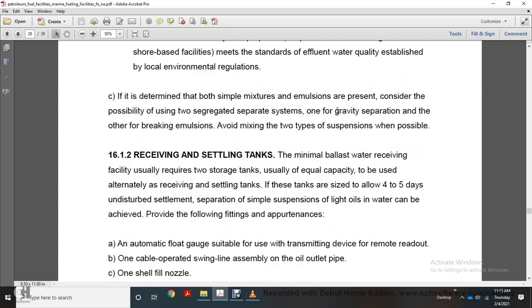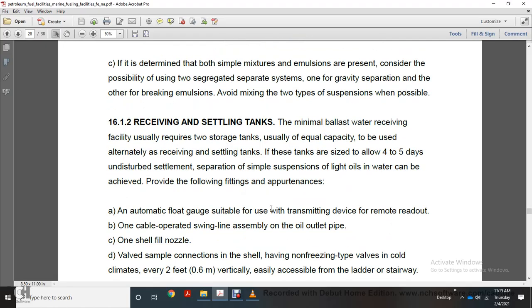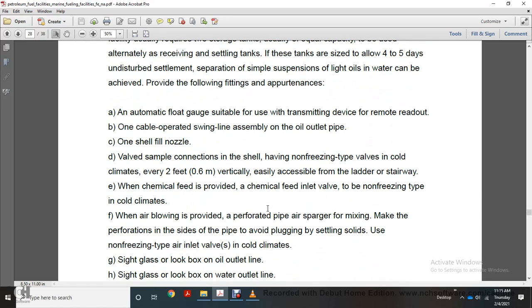Receiving settling tanks. The minimum ballast water receiving facility requires two storage tanks, usually of equal capacity, used alternately for receiving and settling. If these tanks are sized to allow 4 to 5 days of settlement, separation of simple suspensions of light oils and water can be achieved. Provide the following fittings and appurtenances.